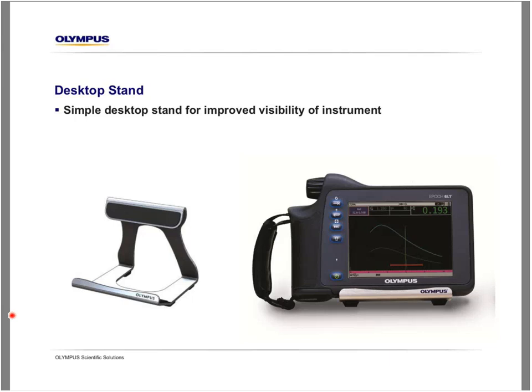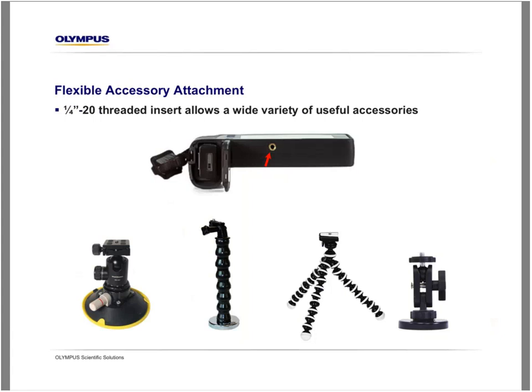Now, we do have customers that would like to be able to put the instrument down in a field use environment, and this desktop stand is exactly that. It's really for desktop use, so it's not nearly as conducive for field use. But Olympus has considered this as well, and so a final extremely useful component of the mechanical design of the EPOCH 6LT is a standard 1/4-20 threaded insert that's in the bottom of the casing of the EPOCH 6LT. And this 1/4-20, quarter-inch, 20 counts per inch threaded insert is the standard size for almost all camera adapters and accessories throughout the world. So virtually any third-party gooseneck adapter or camera adapter, including tripods, including magnetic, as well as suction cup adapters, these are all immediately usable and adaptable to the EPOCH 6LT.